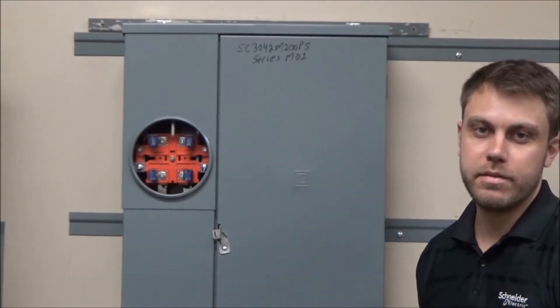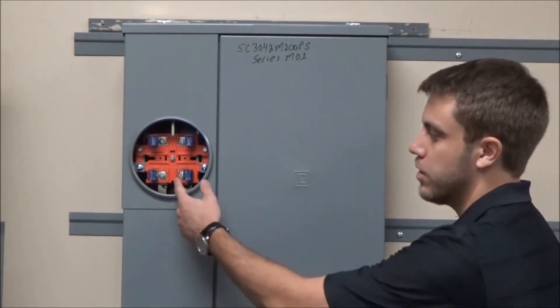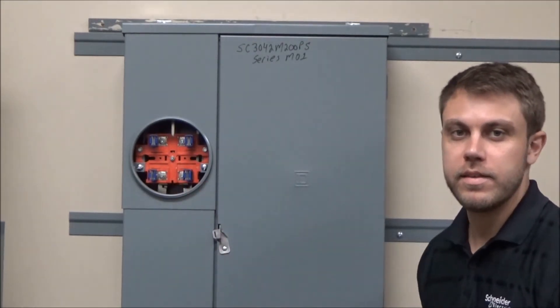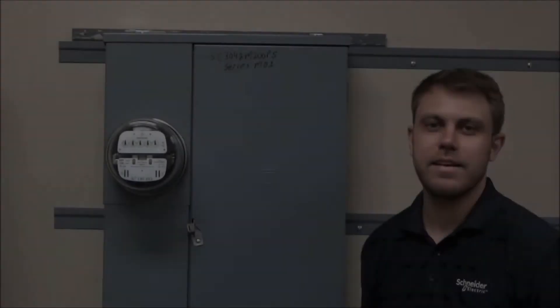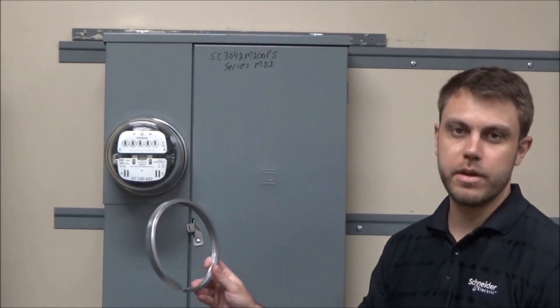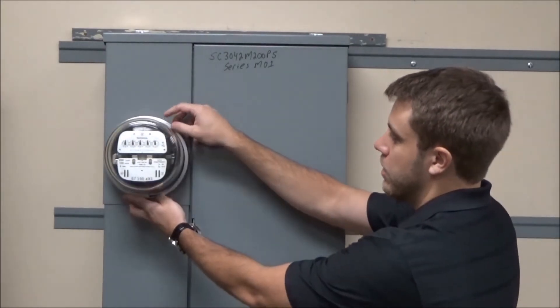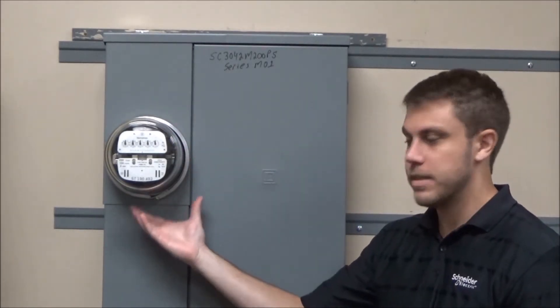In our ring type metering devices, the cover is first installed and secured to the meter socket base, then the utility company will install their watt hour meter. With the watt hour meter installed, the utility company will use their sealing ring to secure the watt hour meter to the lip of the cover and use that to seal it shut.